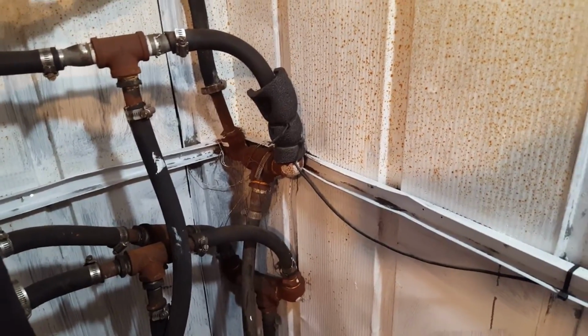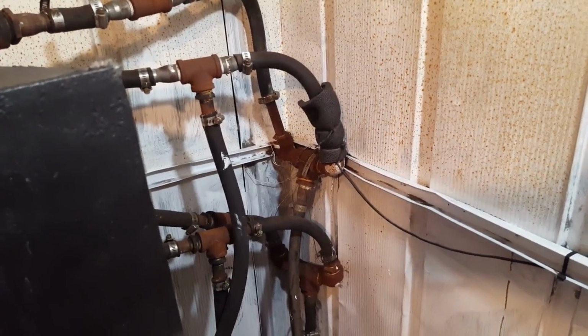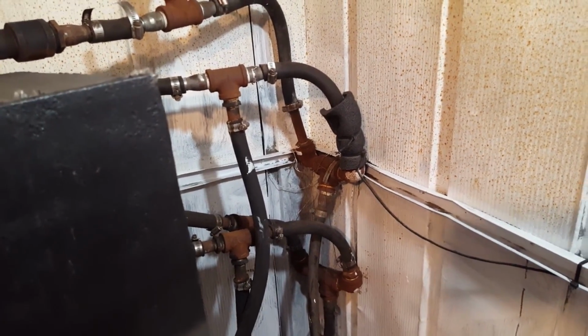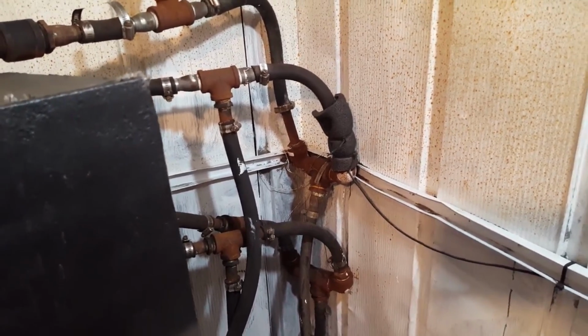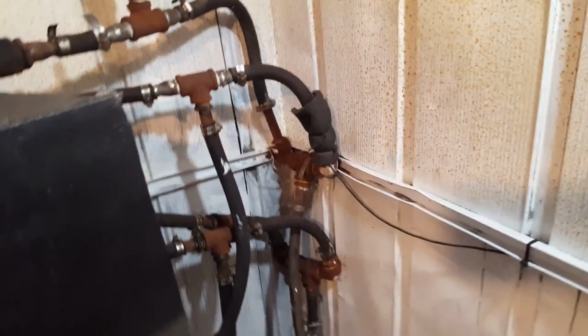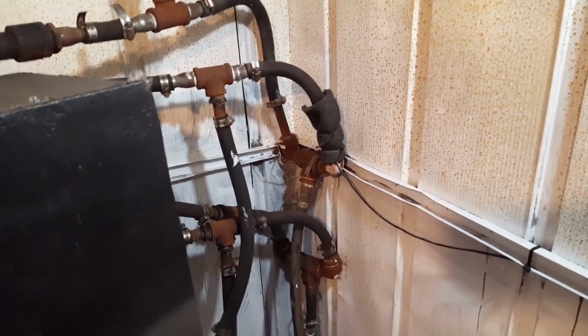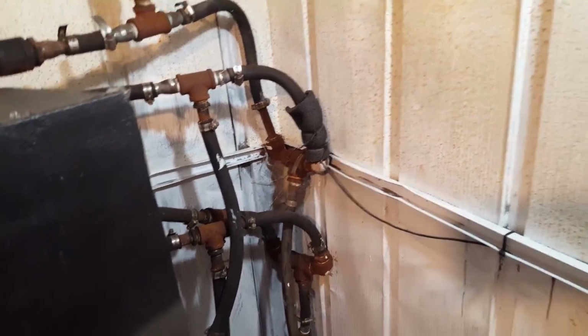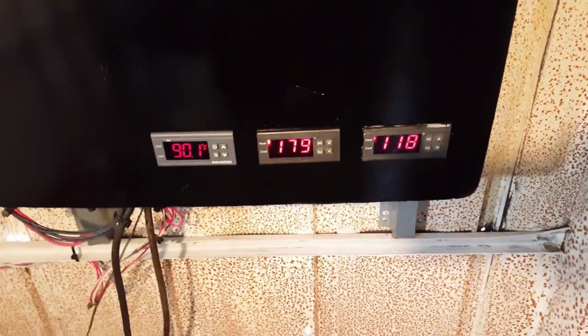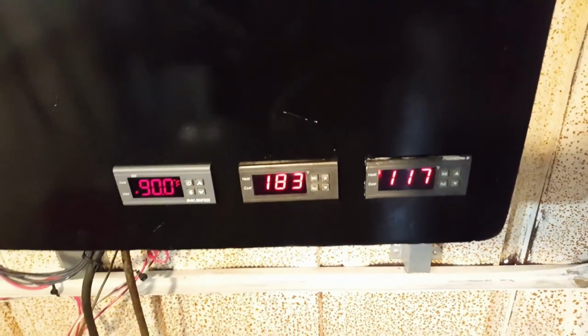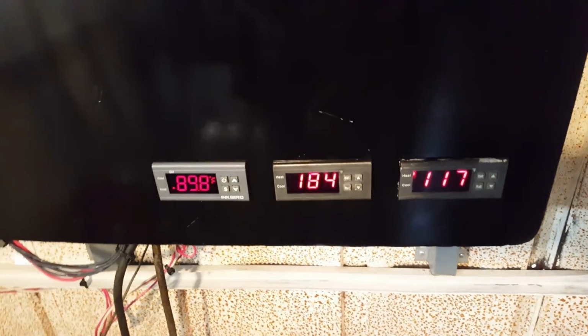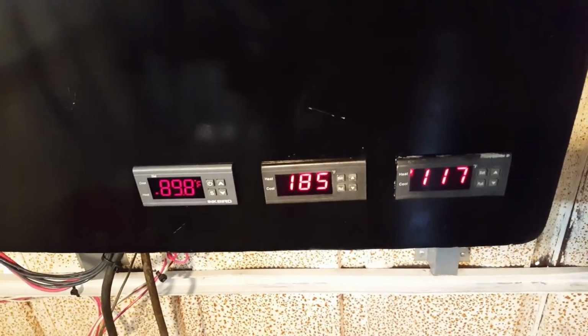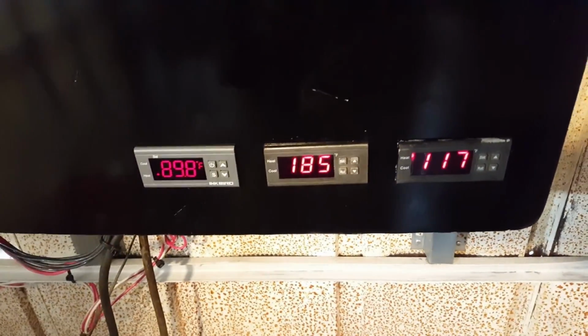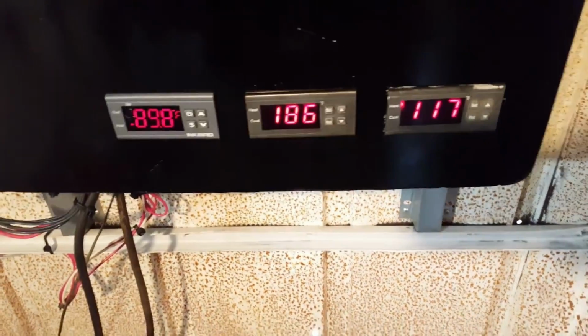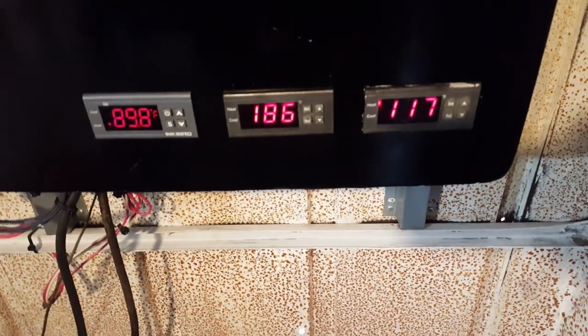There's a temperature sensor right there, and it serves two purposes. One, to let me know what the temperature is of the water running through the system. Two, it is an over temp sensor. If this thing gets close to boiling the water, I want it to shut off. I don't want it boiling water. I don't want it making steam. That is run by this temperature controller on the right. Normally it will give an input to the PLC. If the temperature gets above 194 degrees, it will lose that input and it will shut everything down. Why 194 degrees? Well, that's as high as that temperature controller will go.